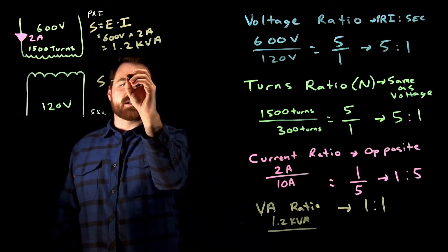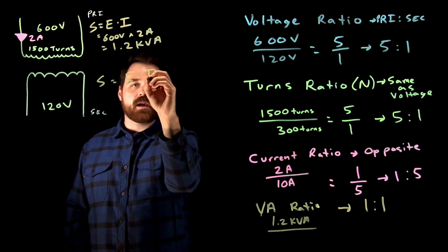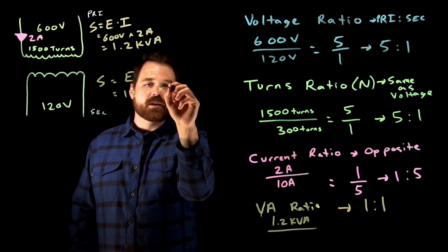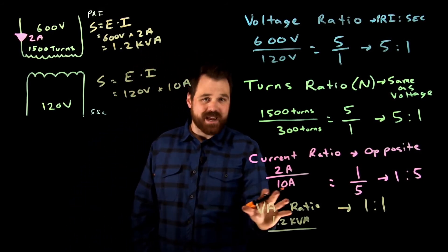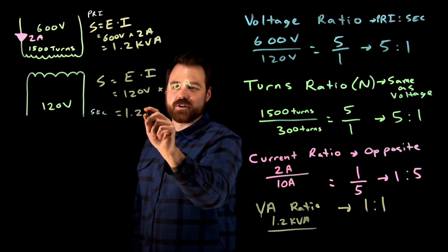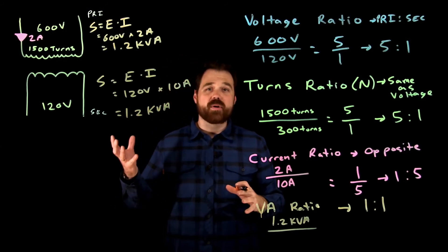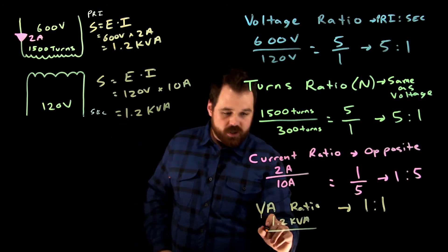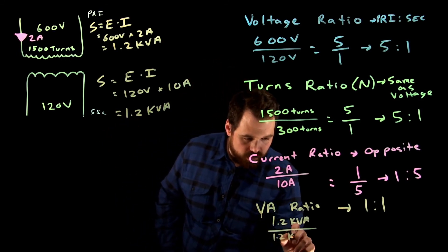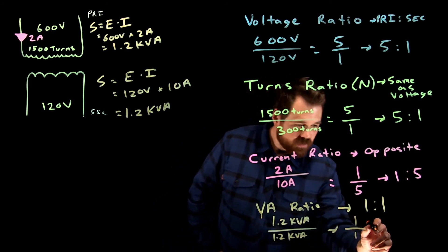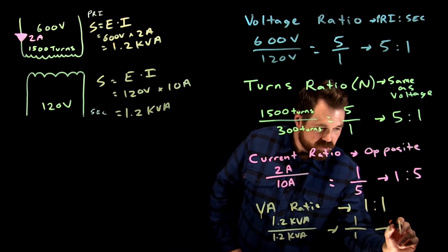Now let's do the secondary. The secondary is again, volts times amps. In this case, it would be 120 volts times 10 amps. 10 amps is what we calculated here. That again is going to give us 1.2 kVA or 1,200 volt amps. So when we put that here, 1.2 kVA, that equals one. So just like we planned, that equals one.